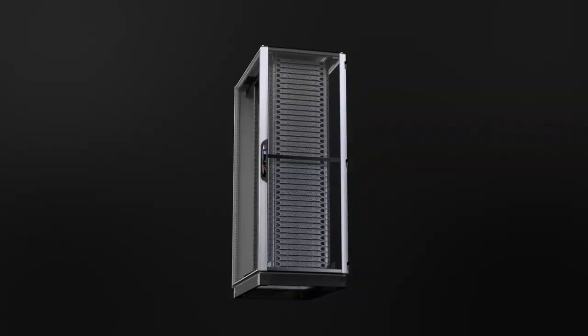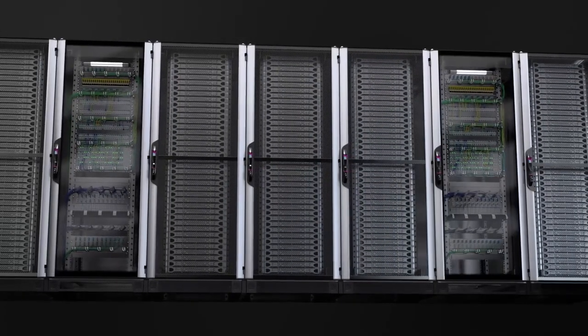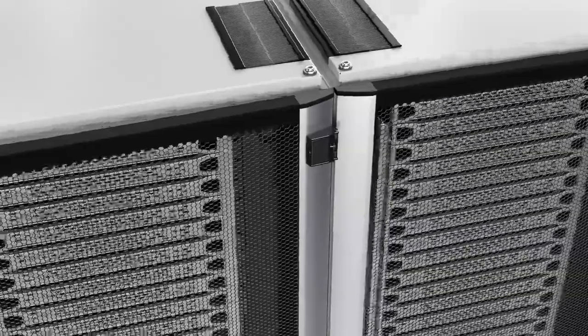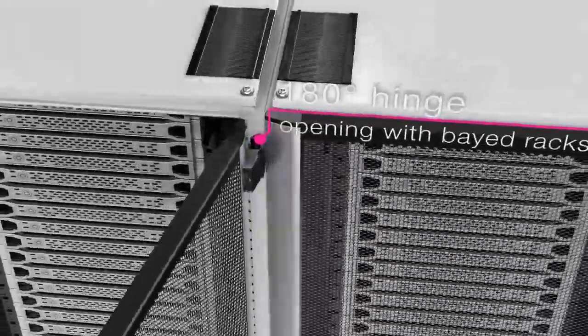For safety reasons, many tenders and specifications prescribe a 180-degree opening angle for racks installed in a row to ensure that escape routes within the aisle containment are not blocked. This requirement will be met by the VXIT with the new baying hinge offering a 180-degree opening angle, even if the comfort handle is in use. This means better access, reduced aisle widths are possible, and escape route safety standards can still be complied with.